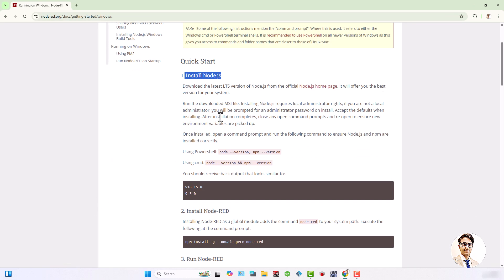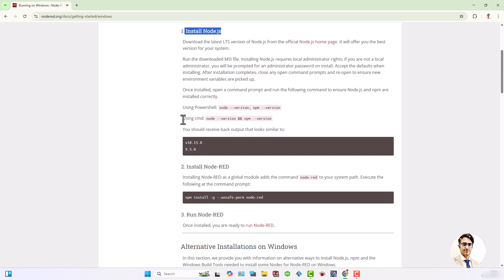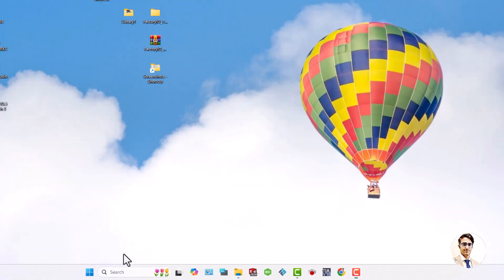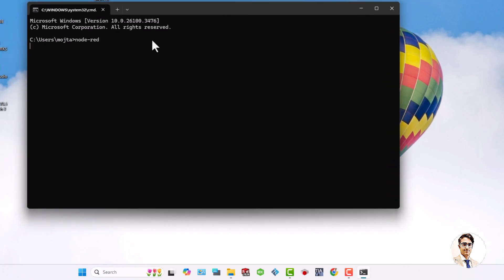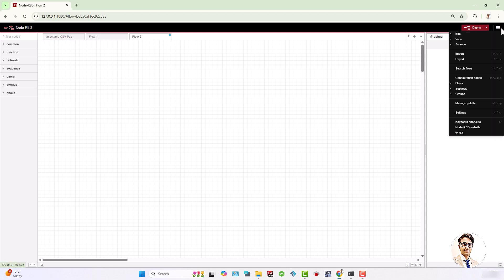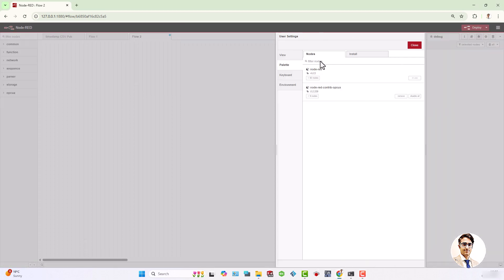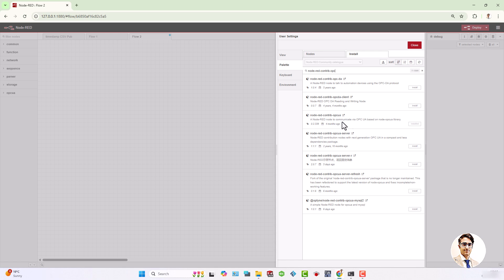Moving on to the next step, if Node-RED is not installed on the PC, it can be downloaded and set up by following the installation guide. Launching Node-RED is done through the command prompt by typing Node-RED, which generates a link to open the Node-RED interface in a web browser. Before configuring the workflow, the necessary OPC UA library called Node-RED contrib OPC UA must be installed. This can be done by navigating to the install tab, searching for the library and proceeding with the installation.